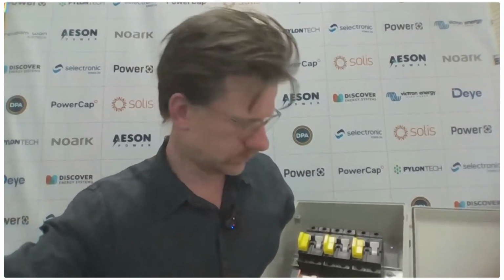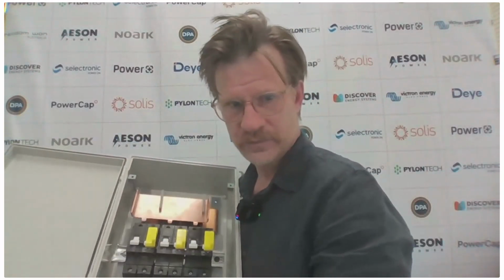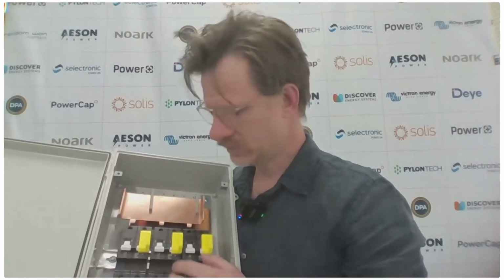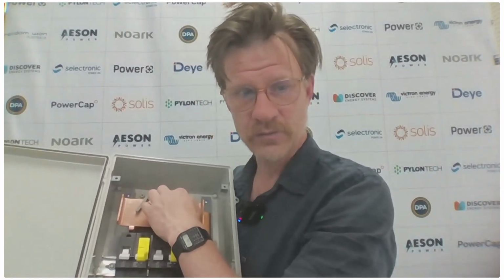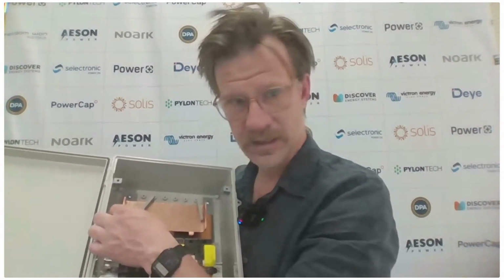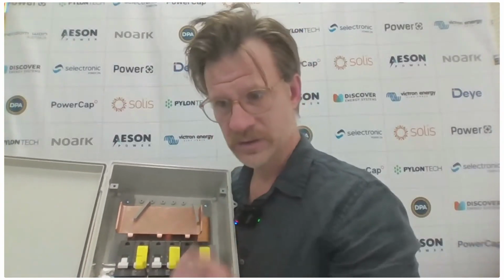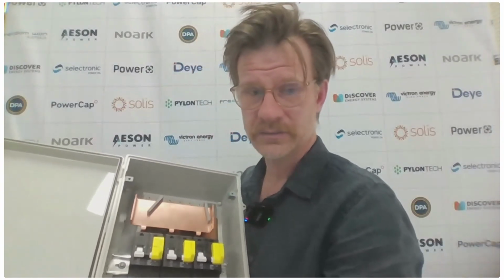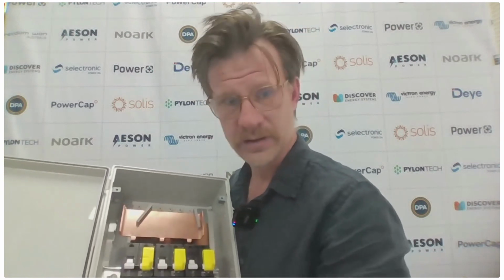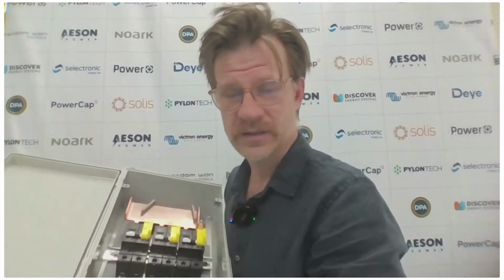We've got these - I've got all these bus bars made up. They're made of pure copper, nice and chunky. The idea is you'll load them into one of these enclosures with 3 circuit breakers, and you put them in. They're designed to have one going one way and the other going the other way, with a spacer in between so they can't touch each other. Then you can take off your inverter cables from the two sides. You can also join them together to make a 6 if you want, but it's really designed to be used like this. That is available now.